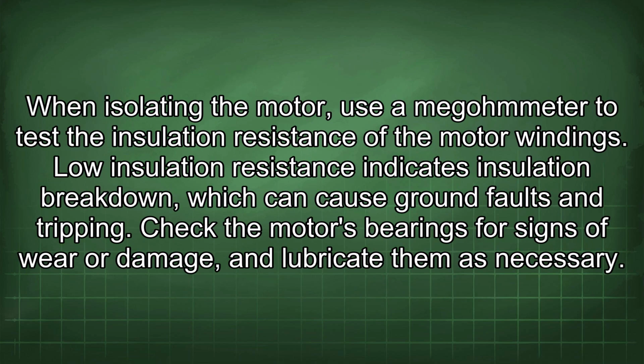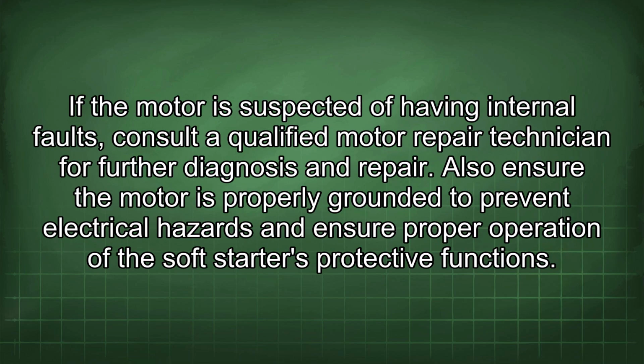When isolating the motor, use a megger to test the insulation resistance of the motor windings. Lower insulation resistance indicates insulation breakdown, which can cause ground faults and tripping. Check the motor's bearings for signs of wear or damage, and lubricate them as necessary. If the motor is suspected of having internal faults, consult a qualified motor repair technician for further diagnosis and repair.